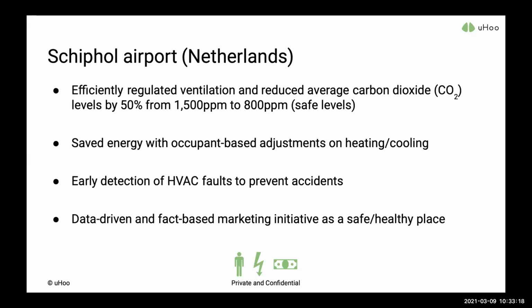Once they understood this, they were able to regulate their ventilation systems inside the building properly, cutting down this pollutant by 50% and keeping it at approximately 800 ppm throughout the day regardless of occupancy. When there are more people inside the space, they have the data and know how to pump up the ventilation system to bring CO2 levels back down to 800 ppm instead of letting it just keep climbing.